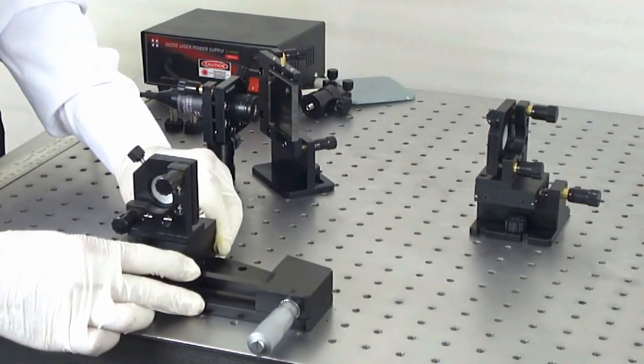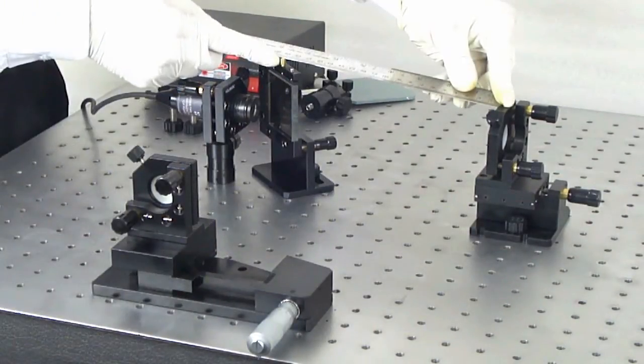The instrument uses diode lasers as a light source. The laser, mirrors, and beam splitter are mounted on precision kinematic mounts for fine tuning and alignment.